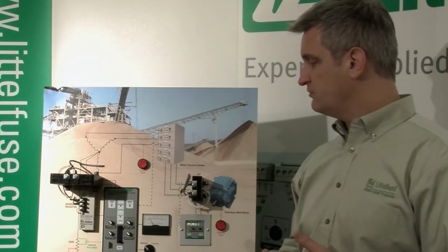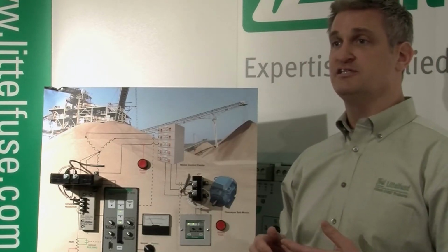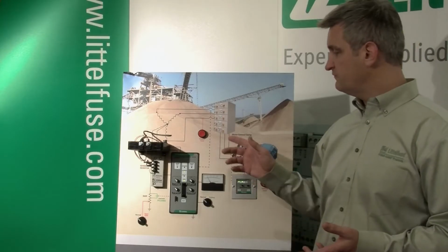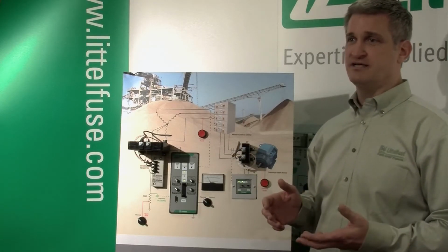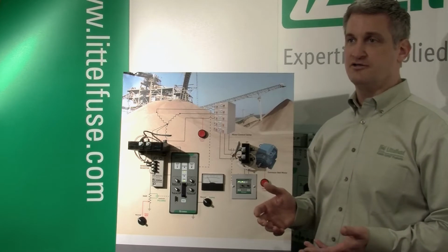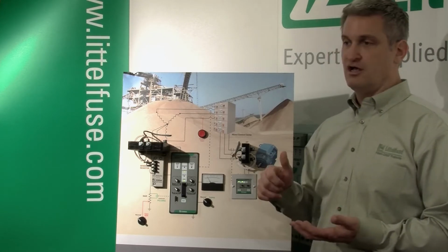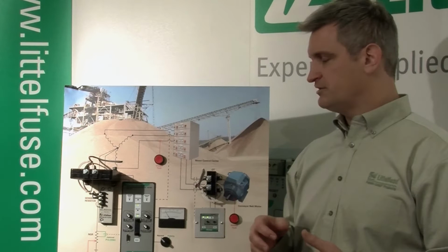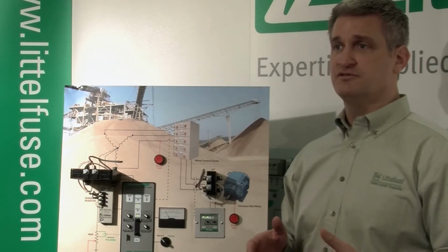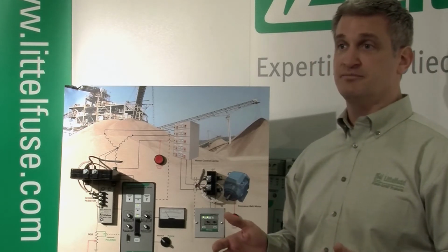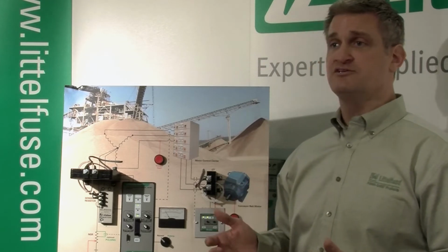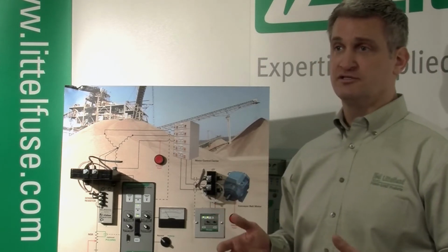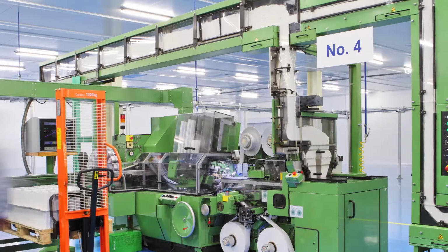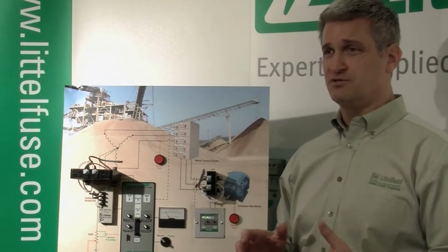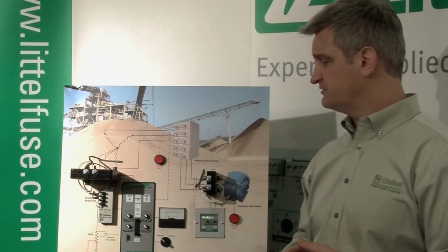The second main reason to use resistance grounding is continuous operation. Because your ground fault current is so low, only 2 or 3 or 5 amps, you don't need to shut anything down. Your processes can stay up and running, and your feeders don't have to be tripped. But in the last 10 or 15 years, with the safety initiative, more and more people are using resistance grounding because of the reduction, or rather elimination, of arc flash hazards for ground faults. So we're seeing it used in hospitals, data centers, and typical manufacturing facilities. We're seeing a growth rate of about 15 to 20% year over year on resistance grounded systems.